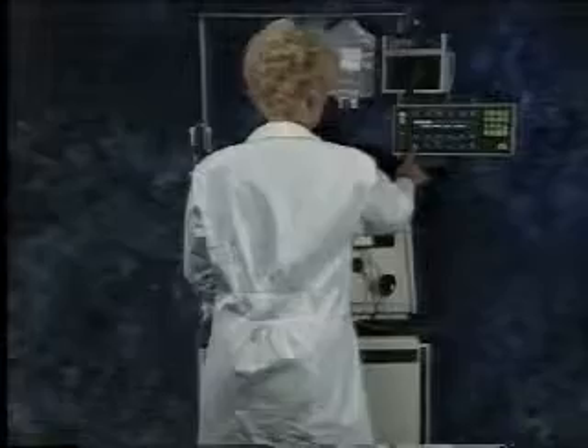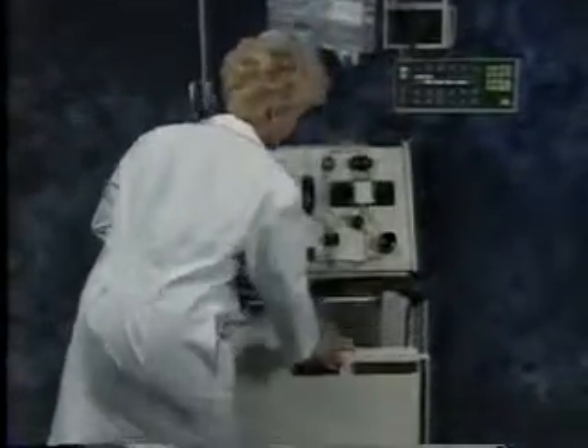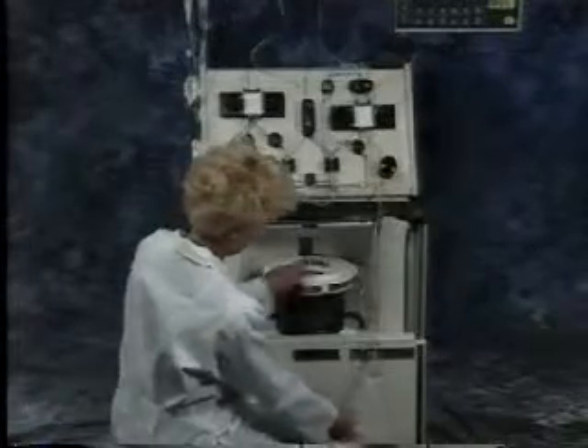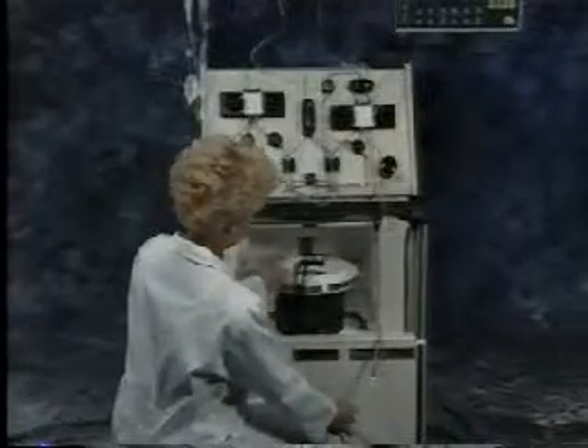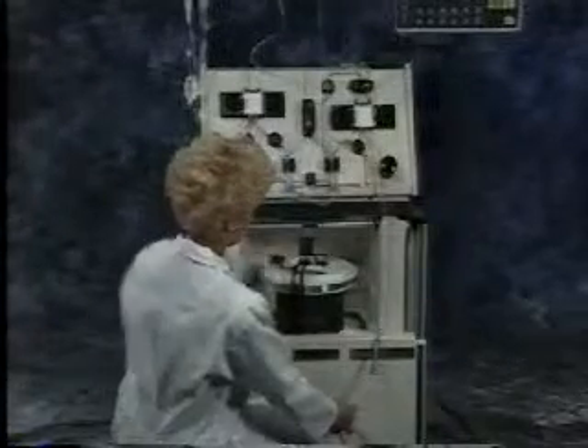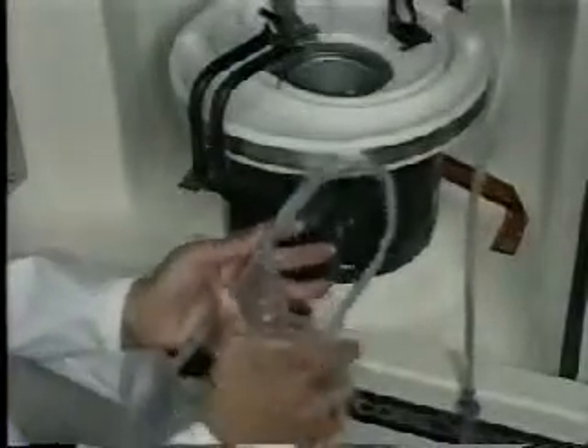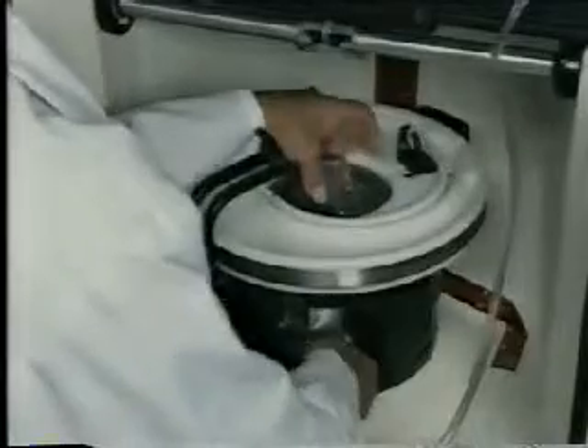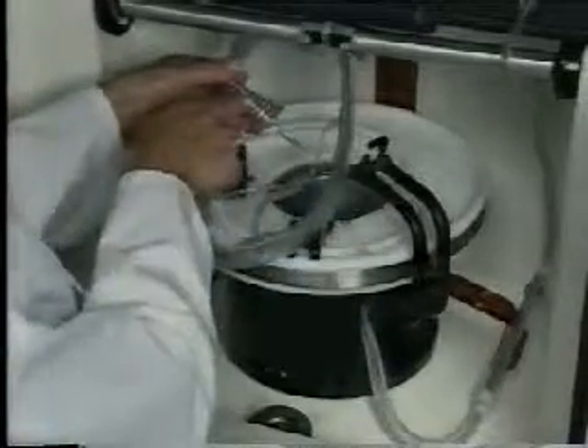Welcome back. We are now ready to load the centrifuge. Press the unlock cover key, slide the cover back, and lower the door. Rotate the centrifuge so that the loading port is open to the front and raise the filler latch. Fold the channel in half, placing the LRS chamber between the folded portions of the channel. Thread it through the loading port and pull it out from the top. Note, a standard ELP set will not have the LRS chamber.